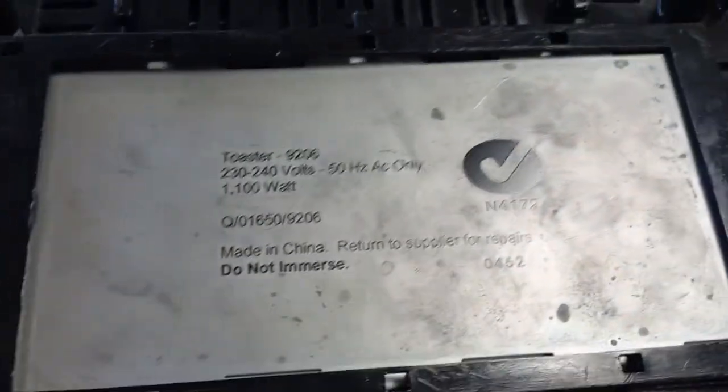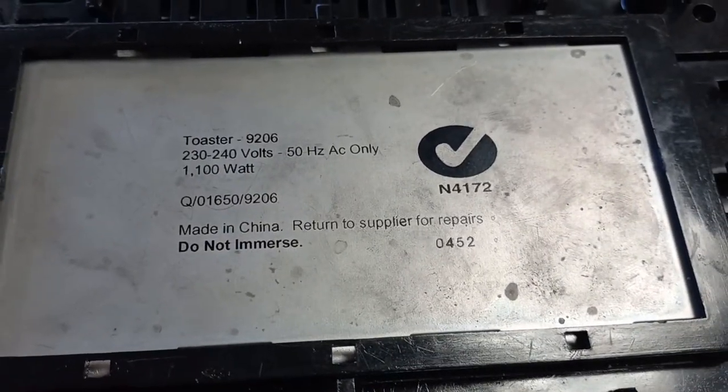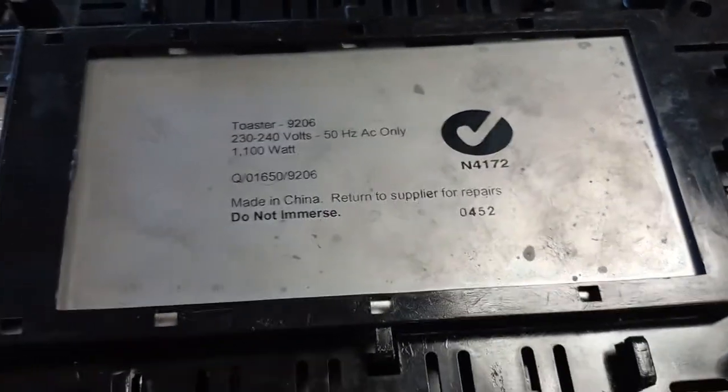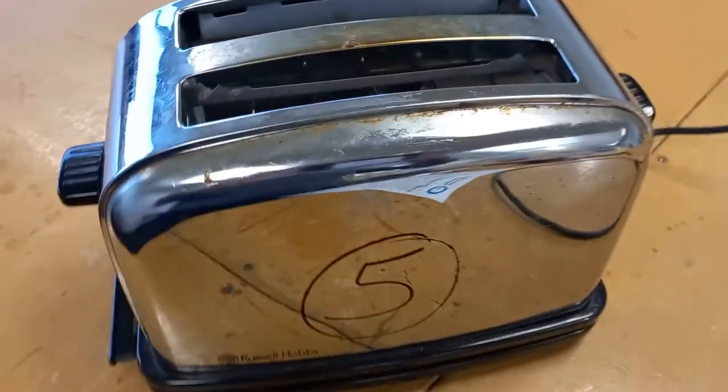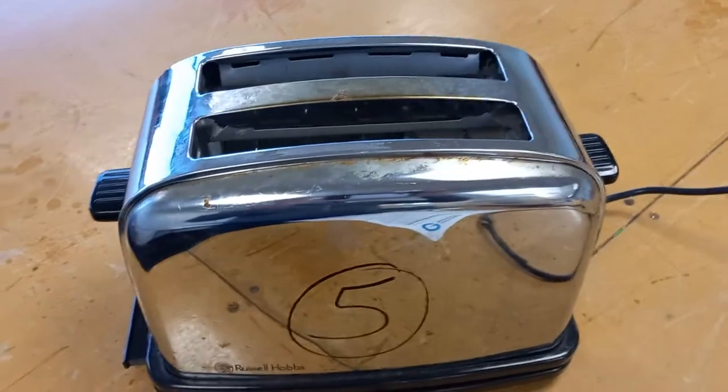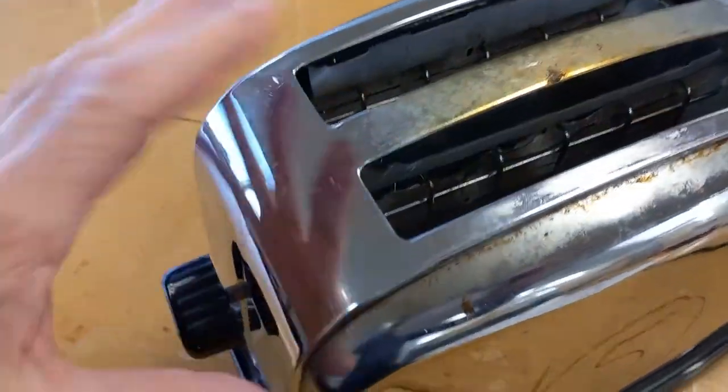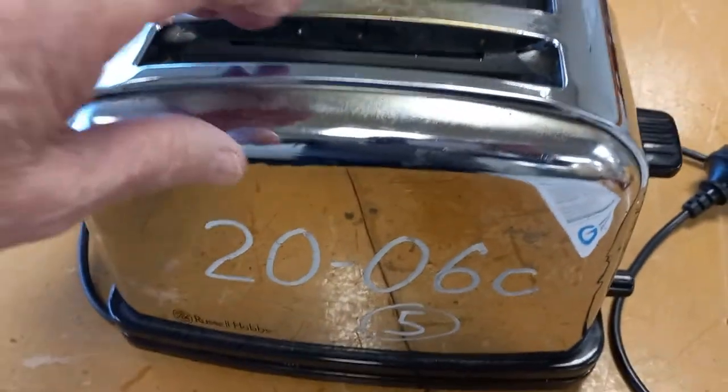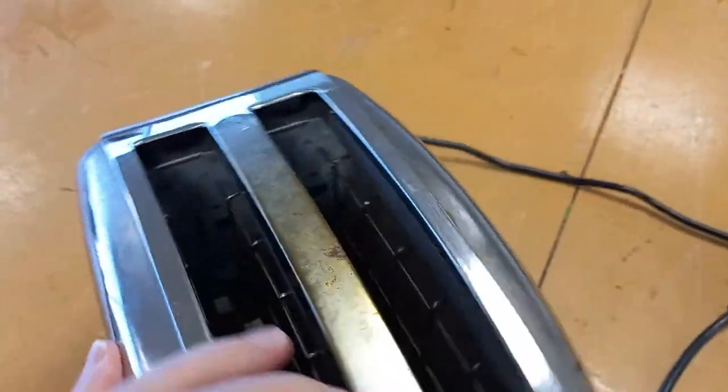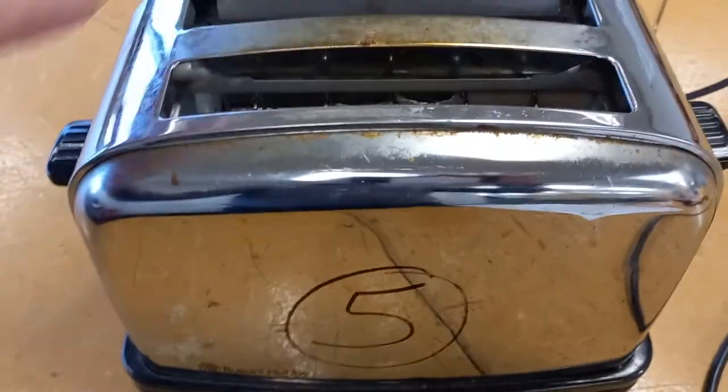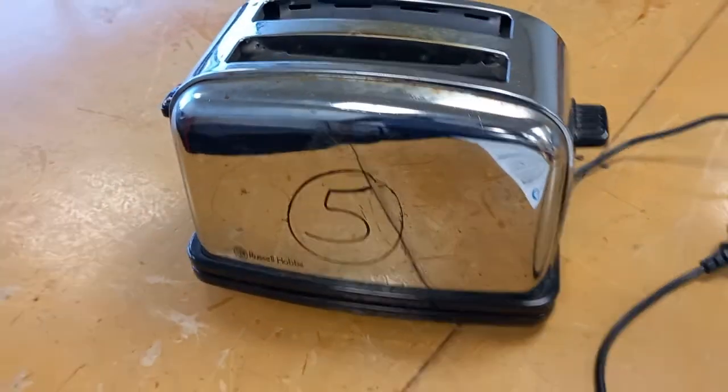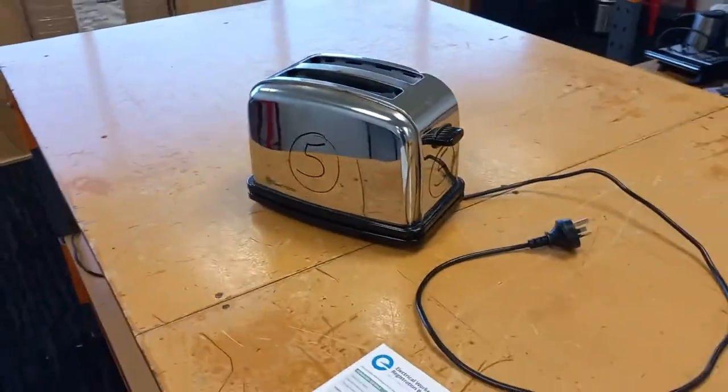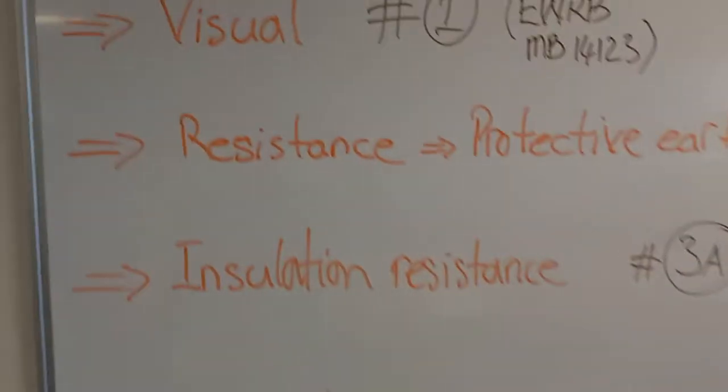This is the nameplate on this particular Class 1 appliance. Then I have a good look at the case, noting if there's any missing covers, missing guards, or anything which would allow for accidental contact with live parts. That is the visual inspection of the Class 1 appliance.